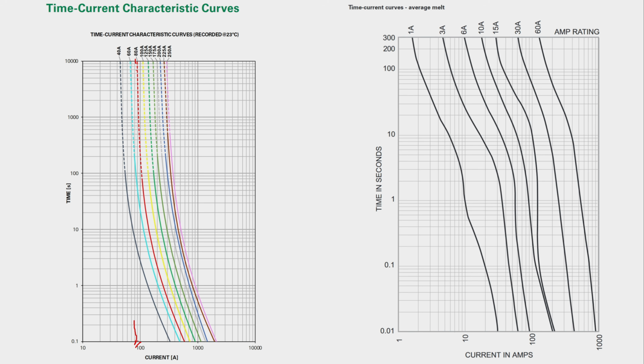That means that an 80 amp fuse won't melt. Even after 10,000 seconds, it's still not going to melt. So that means I must actually choose a lower current fuse. So let me choose a 60 amp fuse, and there it is, the light blue dotted line. So it's this line over here, and there it crosses. So we're getting a crossing about here.